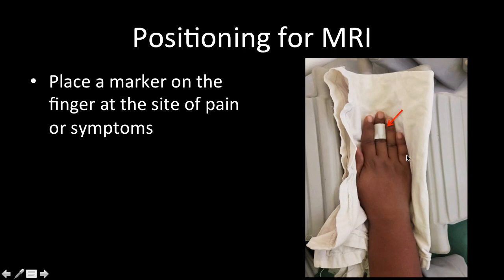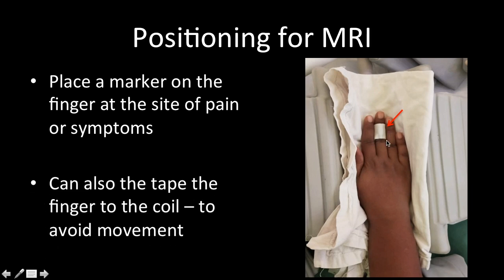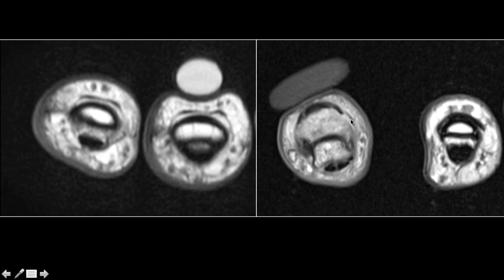The hand should be placed in the prone position with the palm facing downwards on the coil. Make a point to place a marker at the site of pain or symptom in the patient — place the marker superficially and do not press it down. If the patient is making movements, you can tape the finger. The wrong method is pressing the marker down onto the skin, as this deforms the underlying structures and causes you to miss injuries. Please inform your staff to place the marker superficially, or one centimeter proximal to the site of pain, so you don't compress underlying structures.